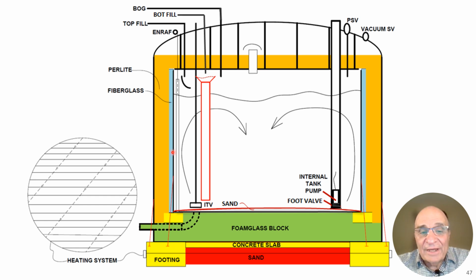If this was all perlite, it would be a solid mass, and something would have to give. Either the outer tank would have to yield, or the inner tank would buckle. And you don't want that happening, so you have this fiberglass layer, because the fiberglass can squeeze and grow. So let's say it's originally a foot of fiberglass, and you squeeze it down to 9 inches, or maybe it's 9 inches after you put the perlite in, squeeze it down to 6 inches, and it has that ability to move as the tank is taken out of service, if it has to be taken out of service.